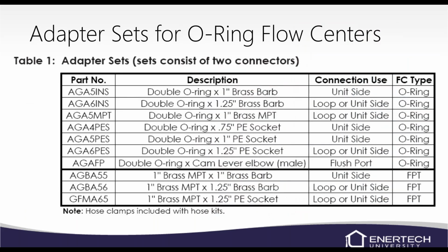We do have adapters for pretty much just about anything you need. We have the double O-ring by hose barb, male pipe thread, the PE socket for the loop side. We have hose barb, MPT fittings. So we pretty much got you covered on the fittings from the unit to the flow center. You get into the bigger units and you're going to use the FPT or the female pipe thread fittings, and the smaller units, probably up to maybe 6 ton or so, we'll use double O-ring fittings.